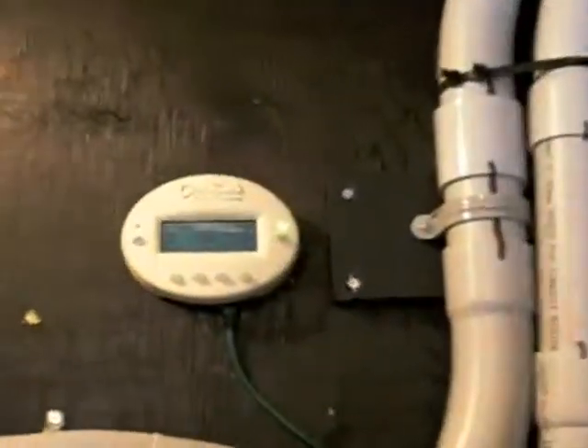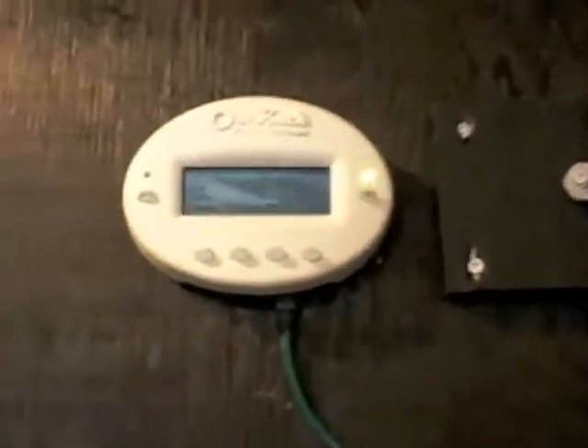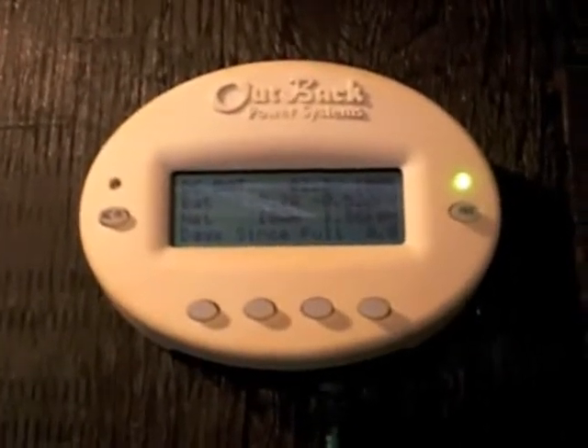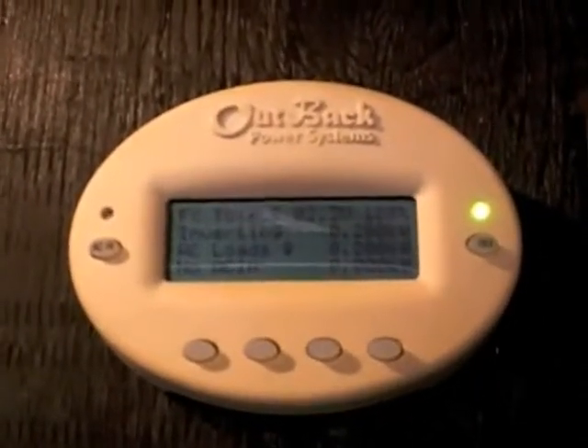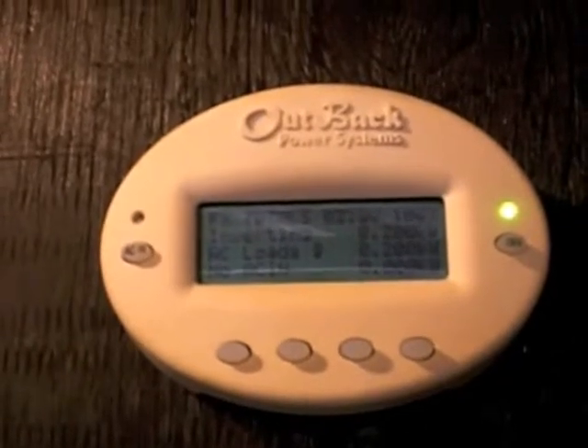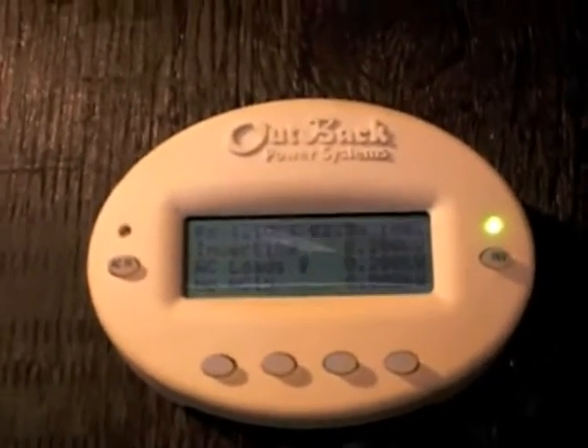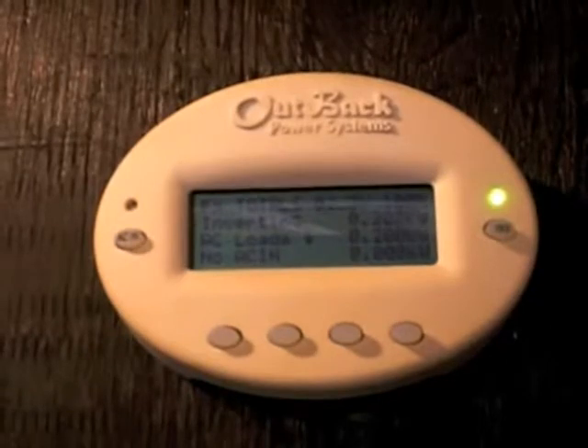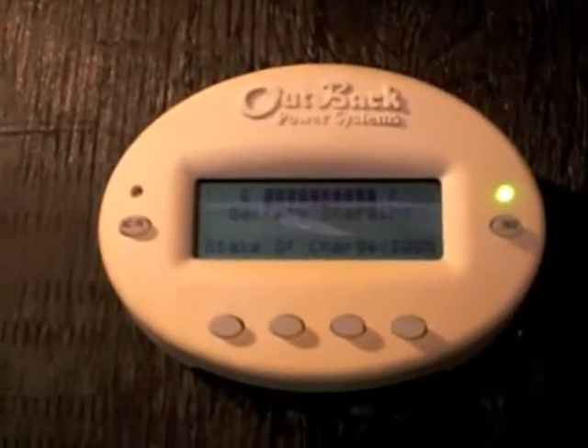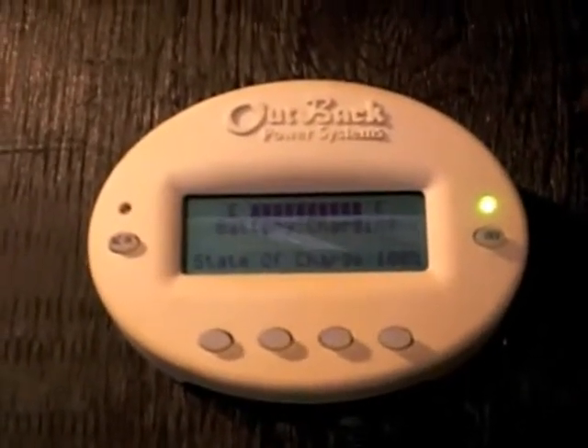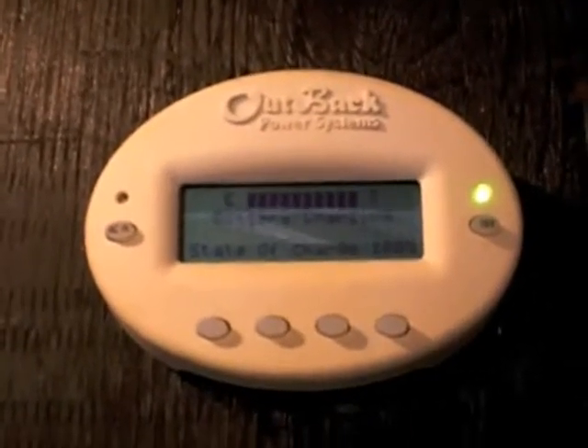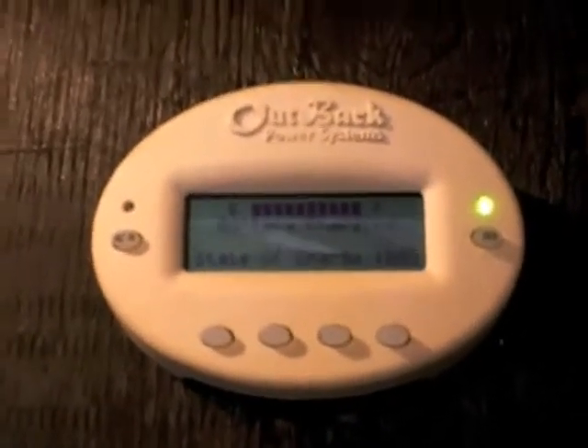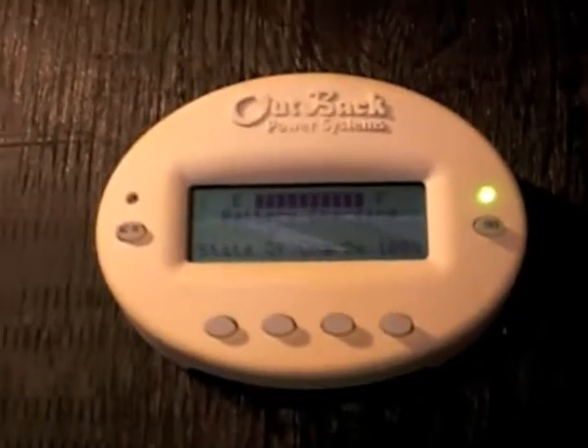All of the activity on this system is being monitored by the Outback panel here, and it's displayed on the Outback hub that we see here. It actually shows us all of the power that comes in and out of this system. This also allows us access to the inverters, where we can program them to take a certain amount of charge from a generator. We can program them to cut out when we want, and we can also tell our generator when to start and stop via this unit. So it's a pretty intelligent little display and control panel.